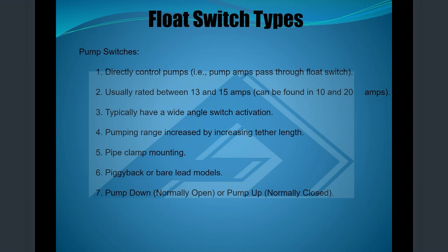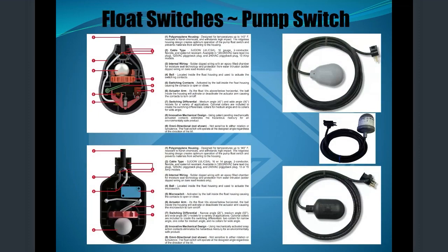Piggyback or bare leads for pump switches. So if you see a piggyback on a float, it has to be a pump switch. It cannot be a control switch. All right, typically they're pumped down, but they can now be pumped up.